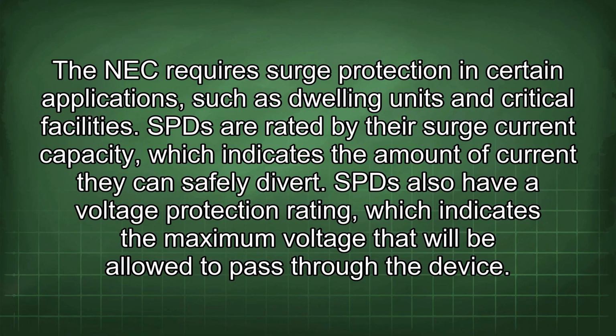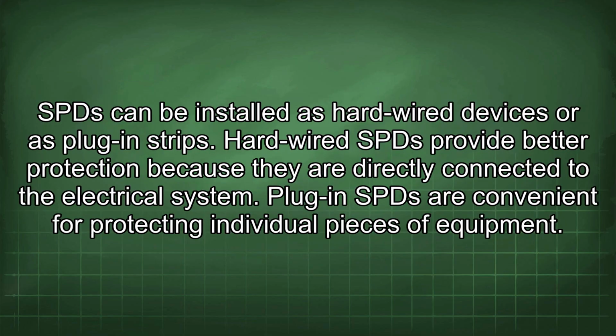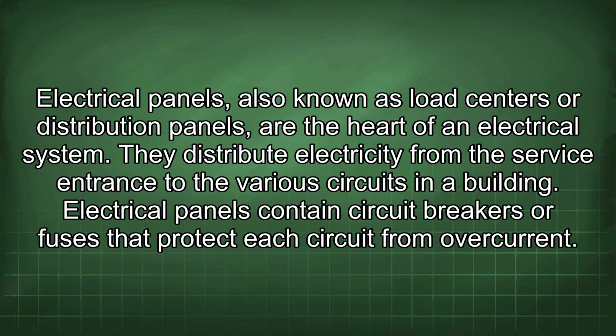SPDs also have a voltage protection rating, which indicates the maximum voltage that will be allowed to pass through the device. SPDs can be installed as hardwired devices or as plug-in strips. Hardwired SPDs provide better protection because they are directly connected to the electrical system. Plug-in SPDs are convenient for protecting individual pieces of equipment. Electrical panels, also known as load centers or distribution panels, are the heart of an electrical system. They distribute electricity from the service entrance to the various circuits in a building.